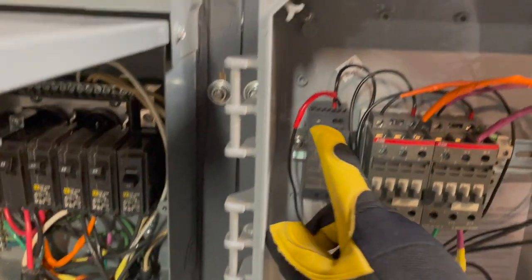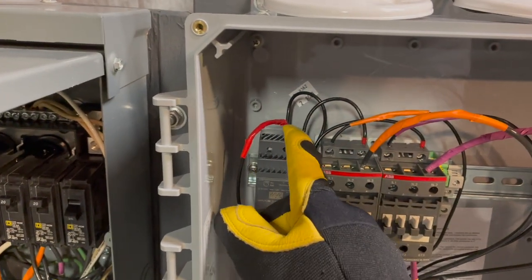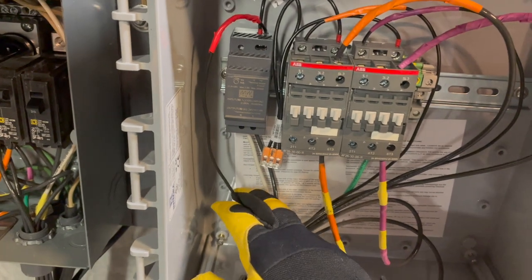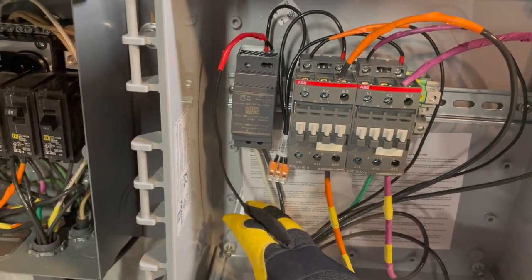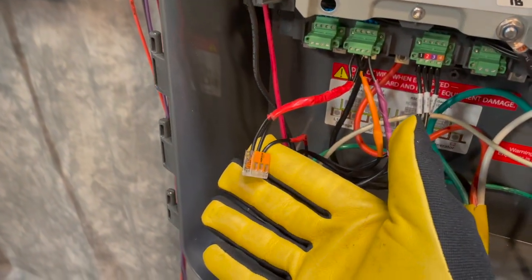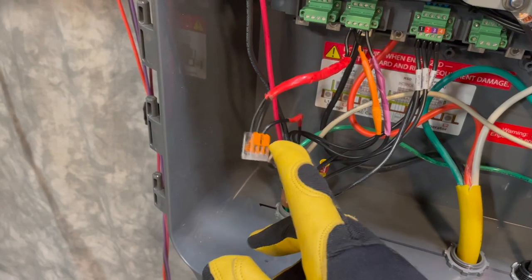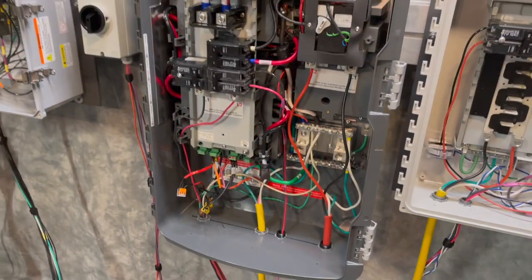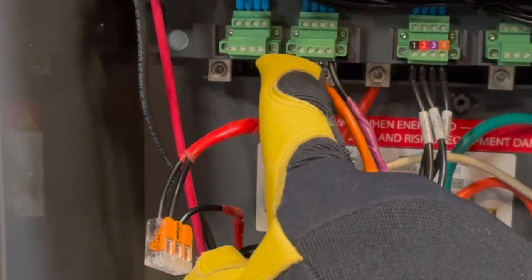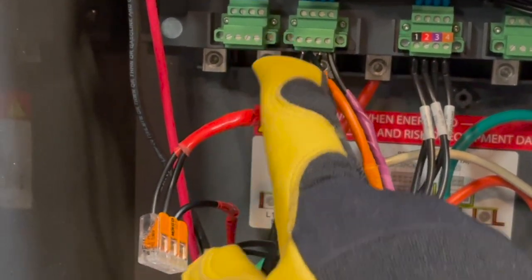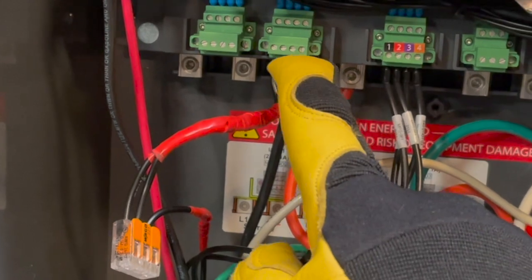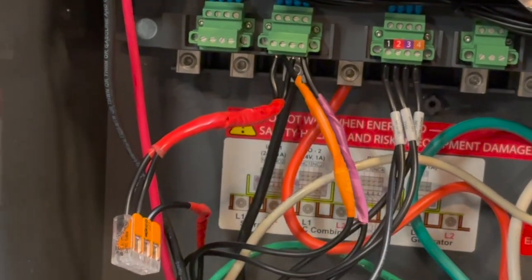Then the positive circuit leaves here and that's going to become your switch leg. Notice I've only used a single wire because I've split that positive into two over here in the IQ System Controller and landed it on NC1 in on the left and NC2 in, the third screw over.